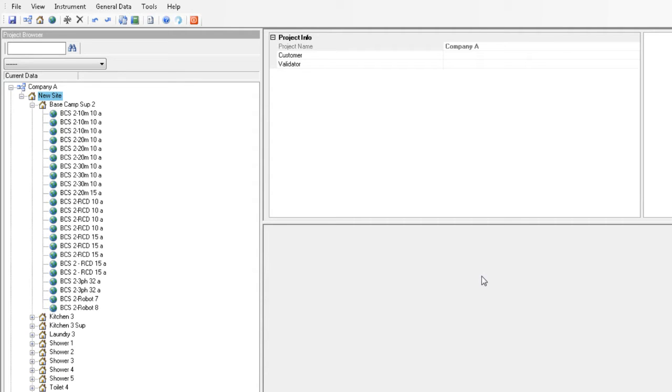If you just update and if you're still running Windows 7 and you update, you shouldn't lose any information. There is a backup utility which I can show you how to do. It's included by Metrel to back up your data. The only downside is that when you restore the database back in, it overrides the database and replaces it with that. So I only recommend to do it if you've had a complete data loss. It's not particularly good if you download some data, back it up, and then download more data. When you restore, you'll lose everything and it'll go back to that particular point in time.